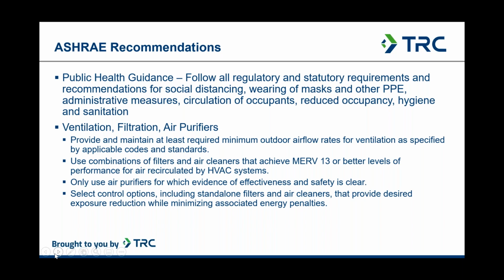And another note, there's a bit of a misnomer out there that the pressure drop through higher grade filters can be prohibitive, that the systems are not capable of handling higher grade filters, that they would have a reduced air volume. That pressure drop is really dependent upon the construction and source of the filters. And in most cases, it is possible to retrofit a system with MERV 13 filters, and just additional attention to filter replacement will need to be made.